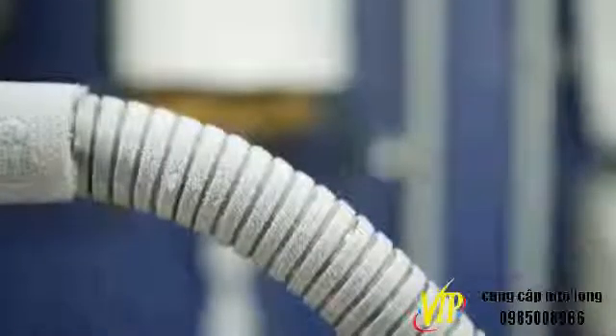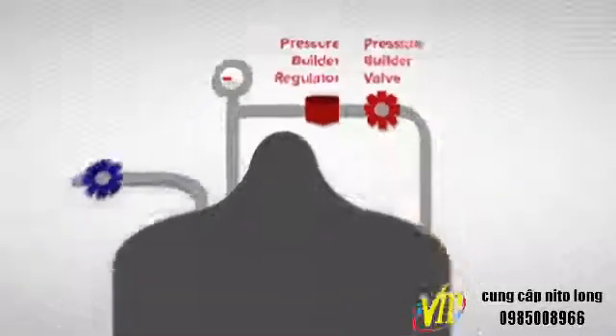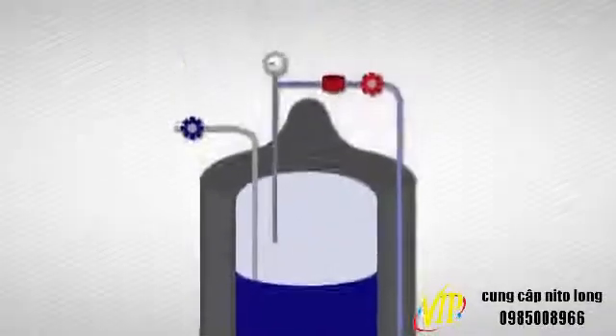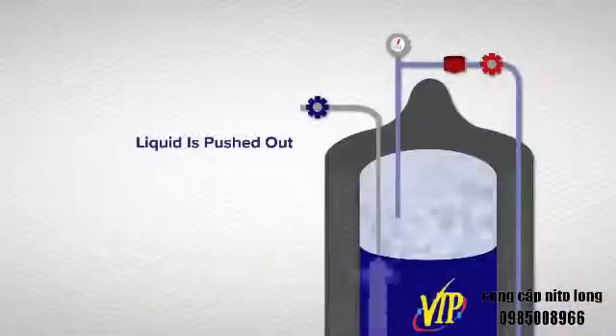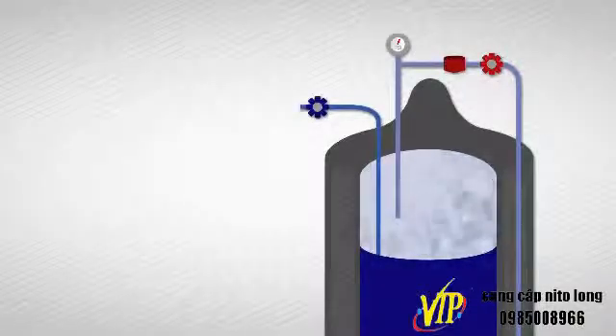For dispensing, connect a manufacturer-approved transfer line for liquid nitrogen. The natural evaporation rate alone is often not capable of providing enough pressure. The tank pressure can be boosted by the pressure builder circuit, with which most nitrogen tanks are equipped. The pressure builder regulator and valve adjust when liquid nitrogen is introduced to the pressure building circuit. Liquid nitrogen in the circuit is turned to gas and delivered back into the top vapor space of the tank, increasing the pressure and allowing liquid from the bottom to be delivered to the liquid valve. Opening the pressure builder circuit will not immediately increase the pressure inside the tank; the process may take several minutes.